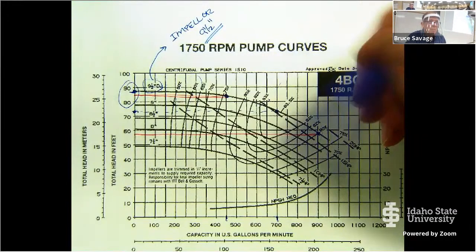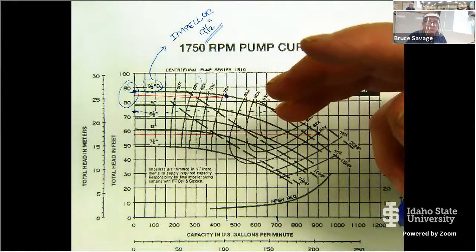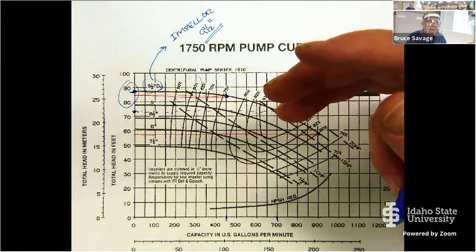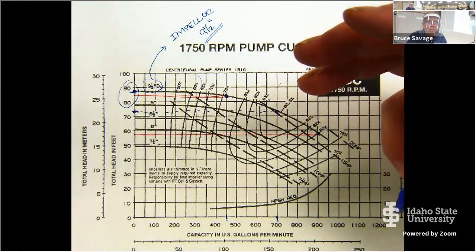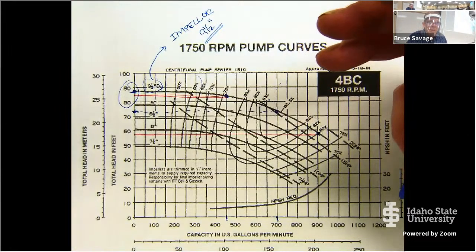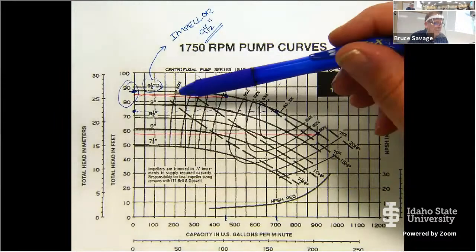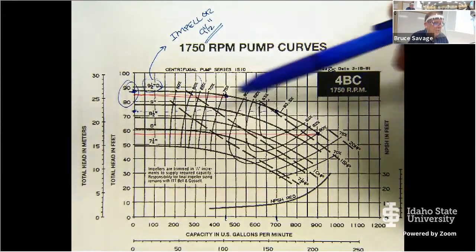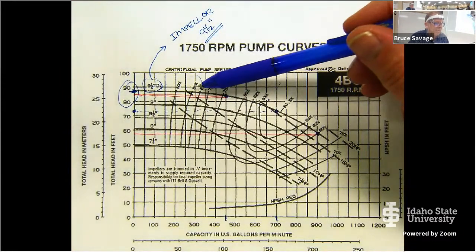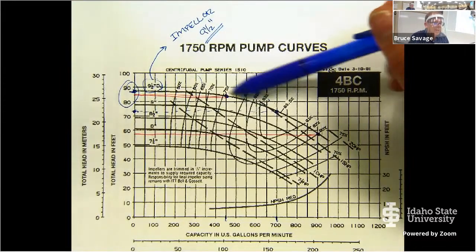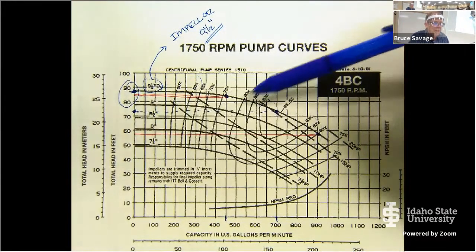This new subdivision is going to be a much higher density, and they're going to put in 19 houses on 1/4 of the land. So they're going to have more houses, but only add 25% more land. And it's like, well, our pump will add 25% more, no problem at all. In fact, I don't think we would have hardly budged down into the best range. We would have come from 60% maybe to the 70 or 80% range on the pump.